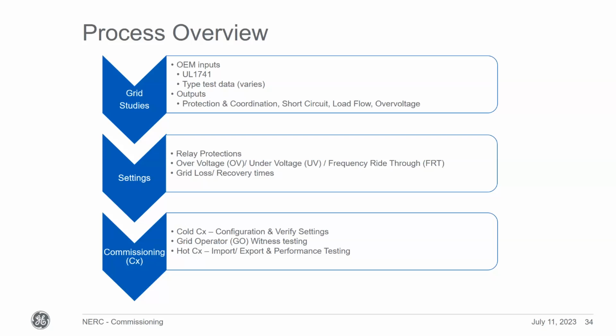After all that's done, the grid operator does the witness tests. What are they mostly looking for? They're looking to verify what we verified, the settings mostly, and then do some energize, and then do some testing on grid recovery and grid loss, making sure the timers are right. Once the grid operator goes away, we get into hot commissioning where we import and export power and run through our performance tests, which include contractually required tests with our customers, as well as any grid requirements for performance testing, which, for example, WEC testing would be covered in this test section.